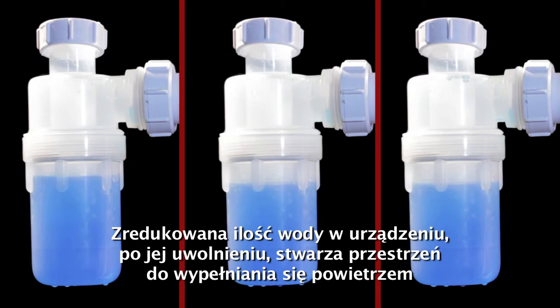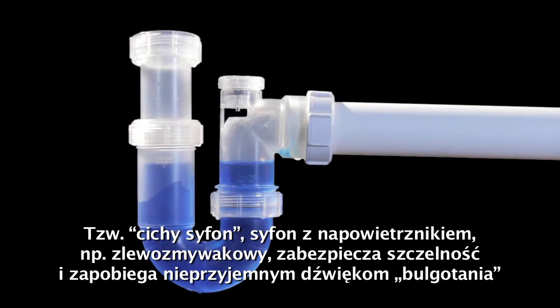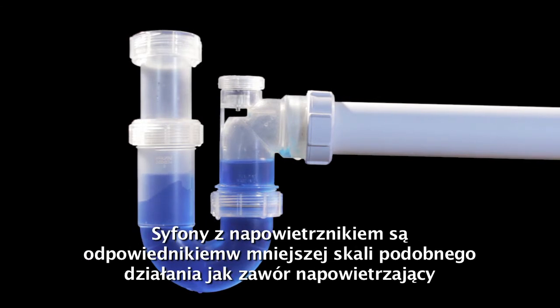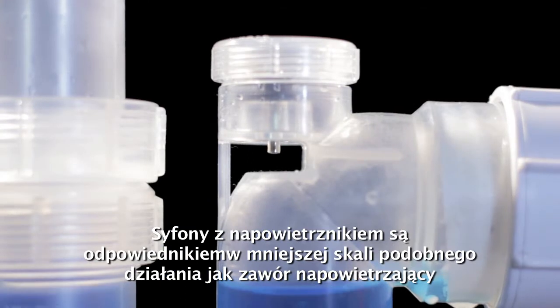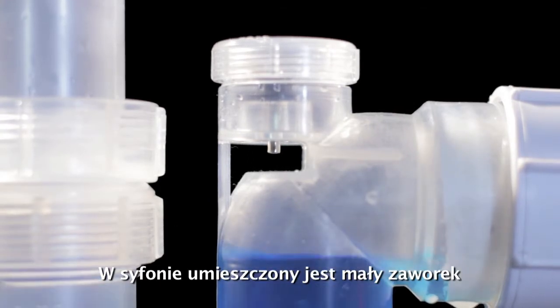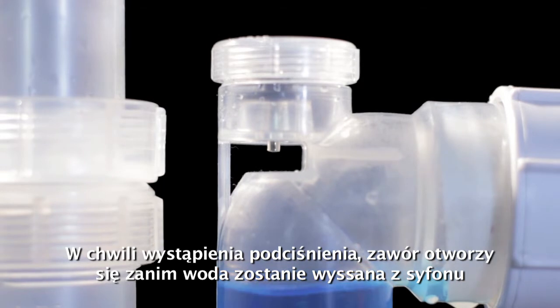A silent trap fitted to an appliance, such as a sink basin, will protect seal integrity and remove unpleasant glugging sounds. Silent traps incorporate the small-scale use of an AAV principle utilising a small valve within the trap. Under negative pressure, the valve opens prior to the water seal being displaced.